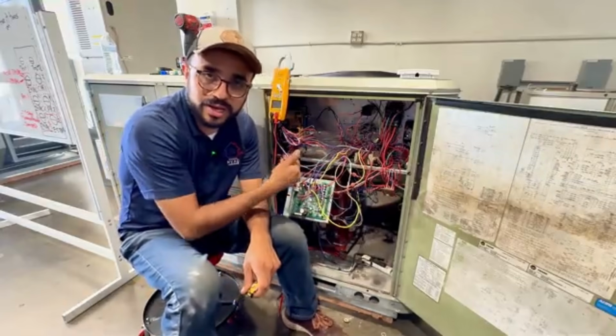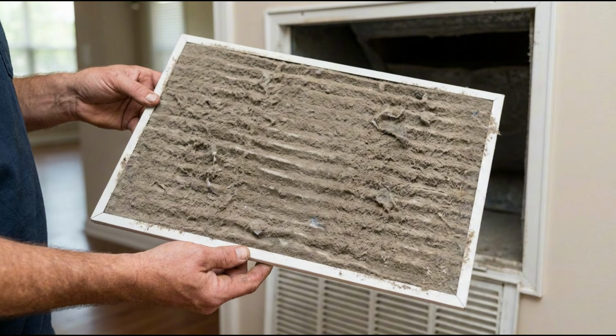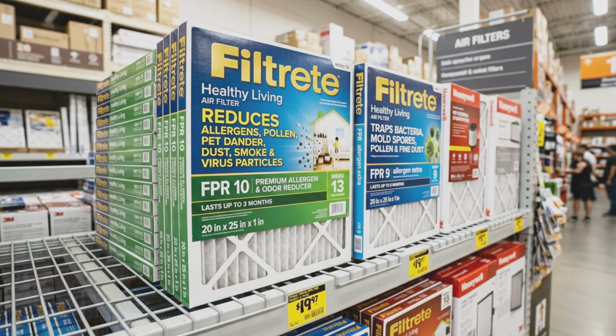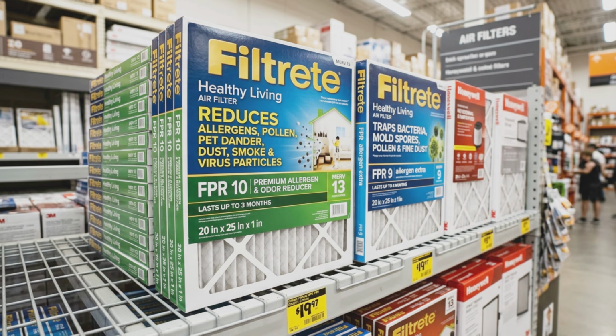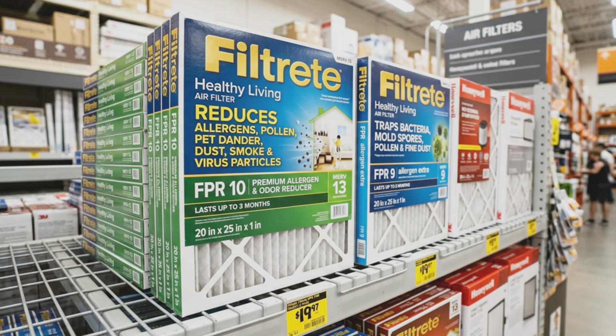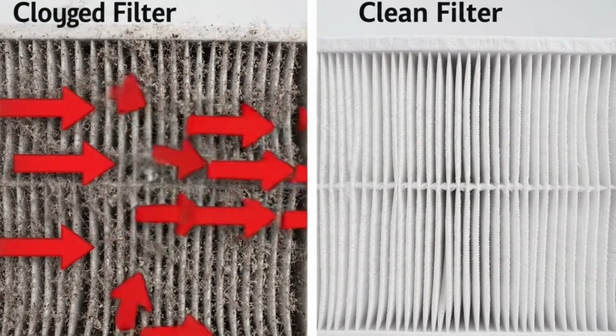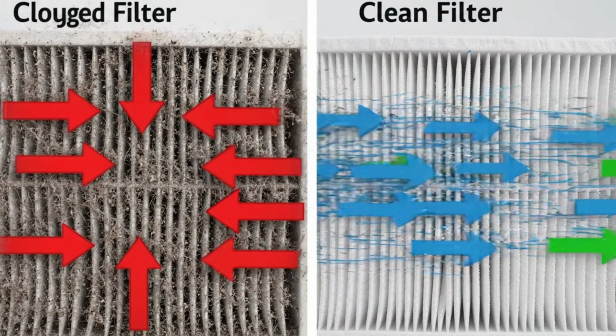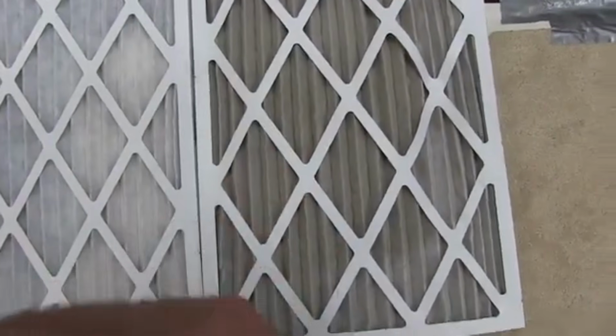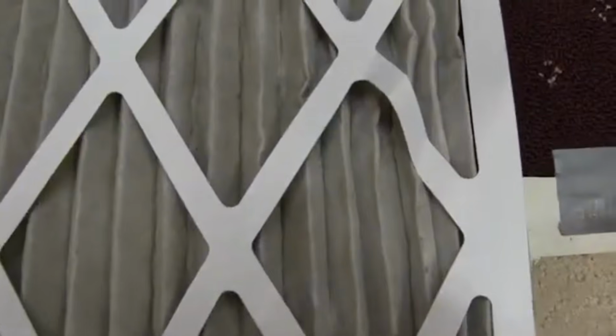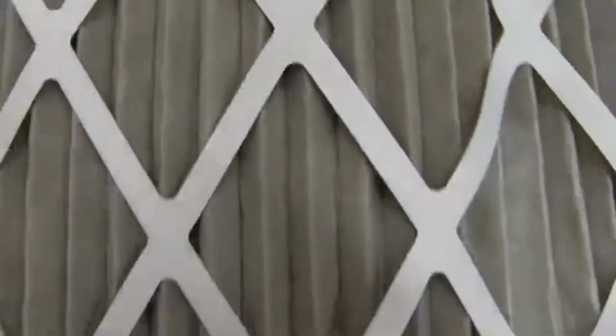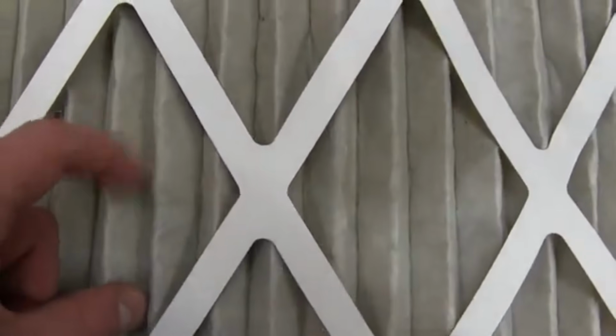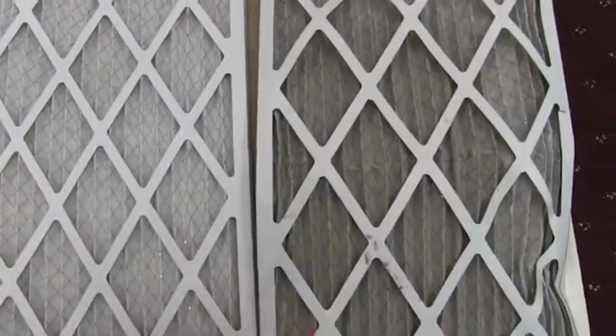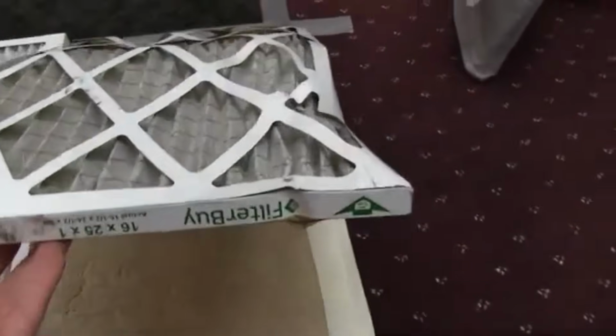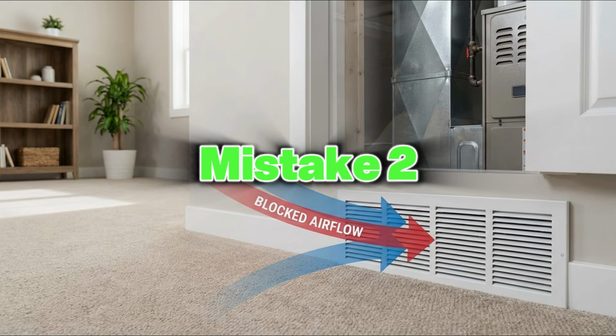Now here's where people get this wrong. They either change filters too infrequently, or they buy the thickest, highest rated filter they can find, thinking more filtration means better protection. It doesn't. A very dense filter creates the same restriction problem as a dirty one. For most residential systems, a filter rated between 8 and 11 on the minimum efficiency reporting value scale, changed every 60 to 90 days, is the sweet spot. Enough filtration to protect the equipment without starving it of airflow. Set a calendar reminder right now. That's all it takes.